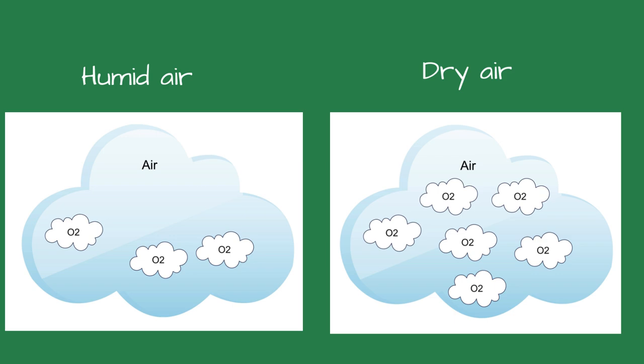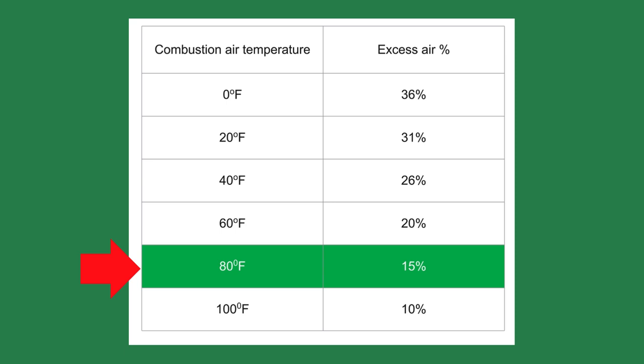Let's see how this works on your job site. You install a new boiler in August or early September and adjust the air to fuel ratio for 15 percent excess air or 3 percent oxygen. The combustion air for the boiler is connected to the outside using a PVC pipe. The outside air temperature is 80 degrees with no rain. Your combustion readings show a stack temperature of 250 degrees Fahrenheit and an efficiency of 84 percent.